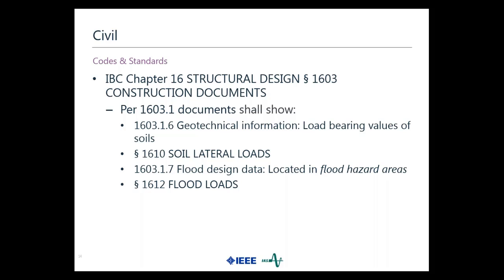1610 is soil lateral loads. And you ask, well, how is that a non-electrical consideration? Well, the interface we're going to have there is - I showed the picture of the electrical room sitting on beams, sitting on some type of support on the ground. A lot of times these electrical rooms are actually put on piers, and if you want to come out of the bottom of that electrical room with your tray, your cable exit, you're going to have to coordinate with those piers.